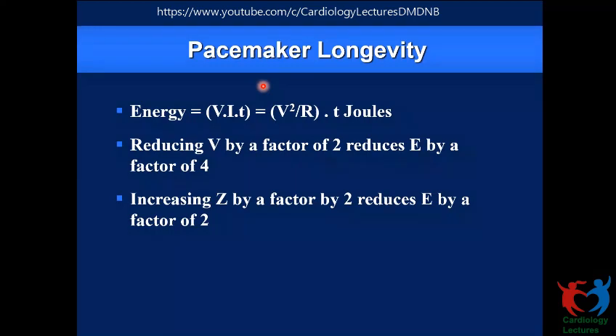But imagine at the same time the polarization impedance becomes very low. That means it allows a lot of current to go. Then that's not efficient. And that is why it's a relative factor. When you're looking directly at the relationship of this, yes, the current outgo is lesser, so you expect you need more energy to capture. But here, because of that polarization impedance, it is going to make it more efficient. As a result, your threshold is lower, so you can program a lower output, and as a result your battery drain is lesser. So it's a more relative concept that you're talking about here.